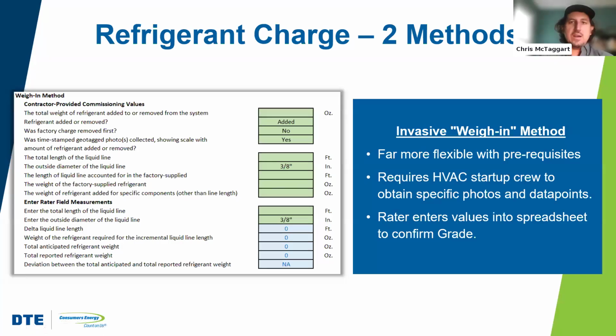Okay, so two methods again. So there's an invasive method as well, which is performed generally speaking by the installing contractor. This actually requires them to weigh in the refrigerant. This should be done by every contractor, most likely. Obviously, some equipment comes pre-charged, but it comes pre-charged for a certain line set length. That's not necessarily always the case for a home. There can be extra value to vacuuming down our refrigerant lines in order to remove any impurities from the system, and then going ahead and adding in the specific amount of refrigerant needed for the home.